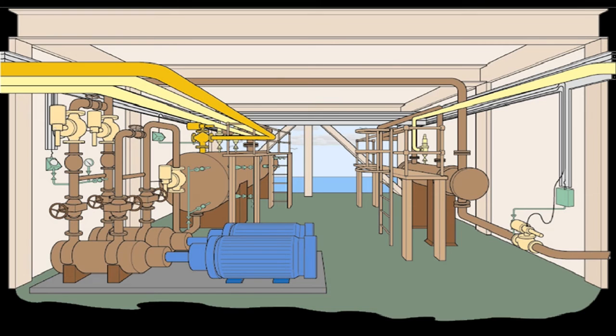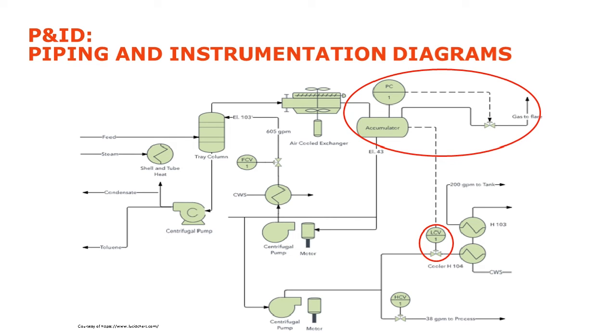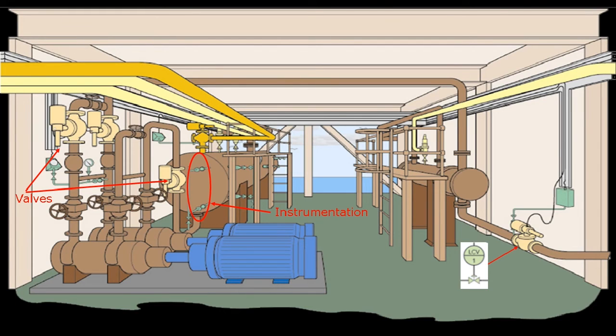If I give you an example, look back to the P&ID we mentioned earlier - we had at the top the pressure control on a valve, and at the bottom level control on a valve. Going back to this image, I can't say for sure, but it's possible that valve on the right, because I see a green instrument line come into it, has some sort of control based off an instrument elsewhere on the plant. So the valves are shown in yellow, the instrumentation in green, and it's possible, for example, that the level in that vessel will instruct that valve to perform a certain function. That's how the P&ID results in a material change in reality.